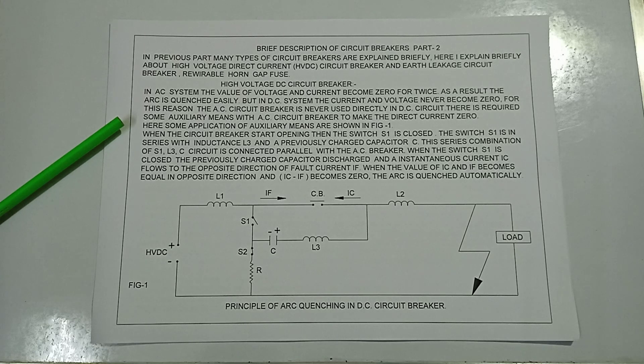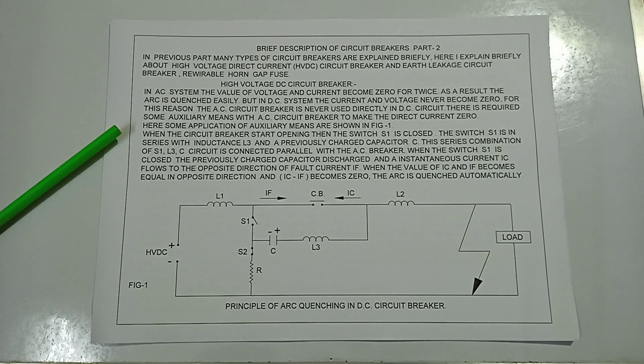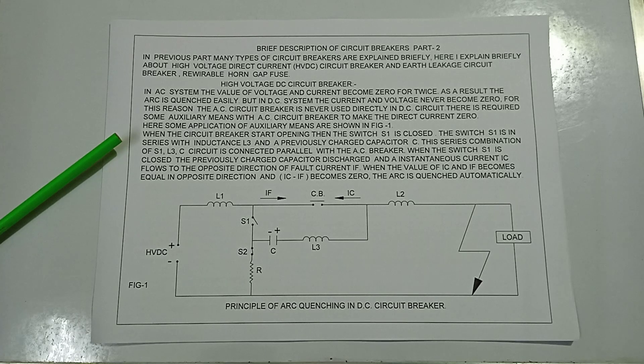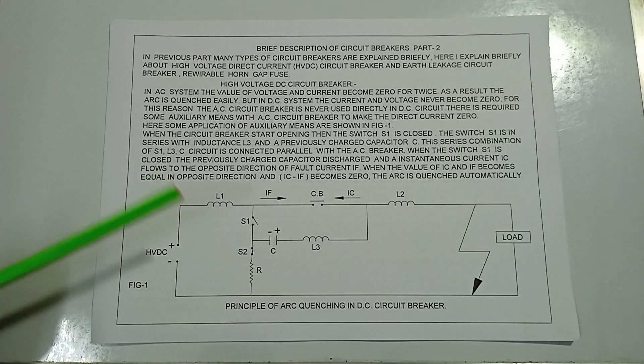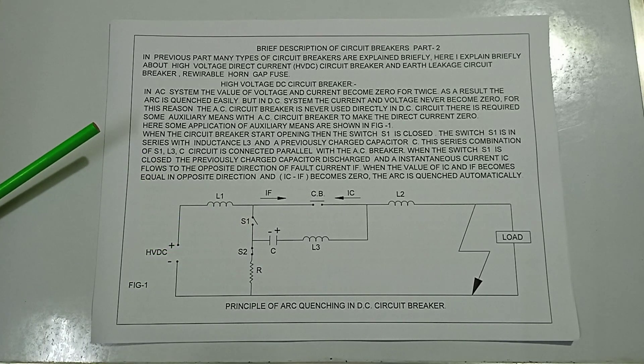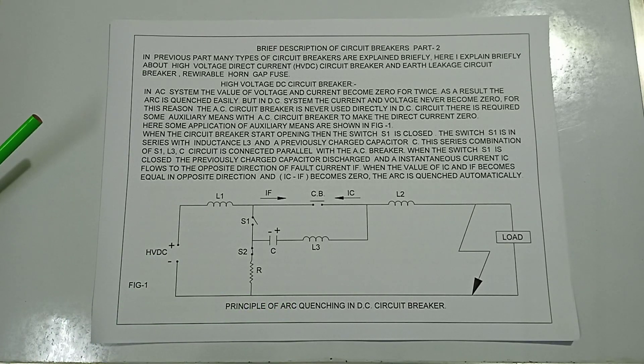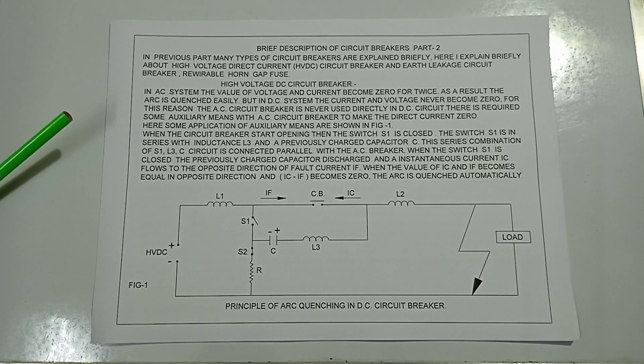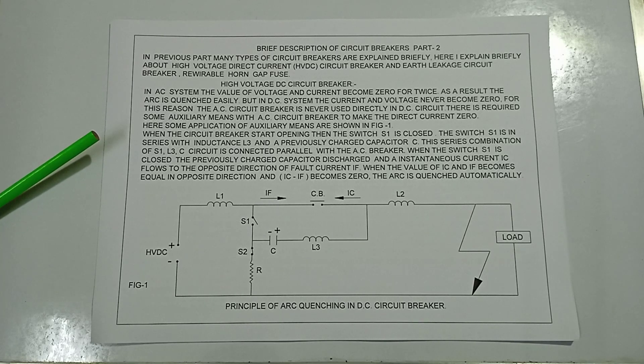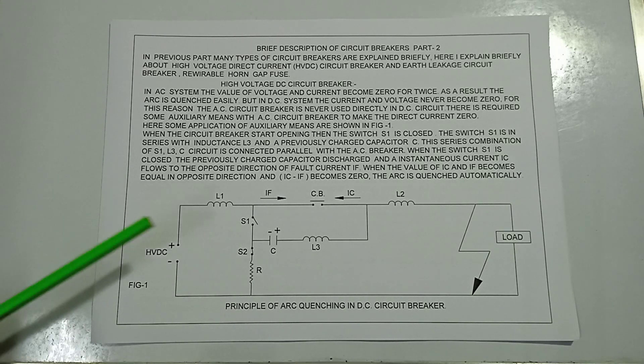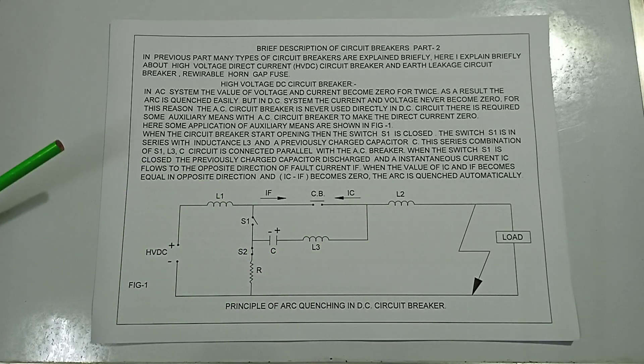Some auxiliary means are required with an AC circuit breaker to make the direct current zero. As shown in Figure 1, when the circuit breaker starts opening, switch S1 is closed. S1 is in series with inductance L3 and a previously charged capacitor C. This series combination of S1, L3, and C is connected in parallel with the AC circuit breaker.